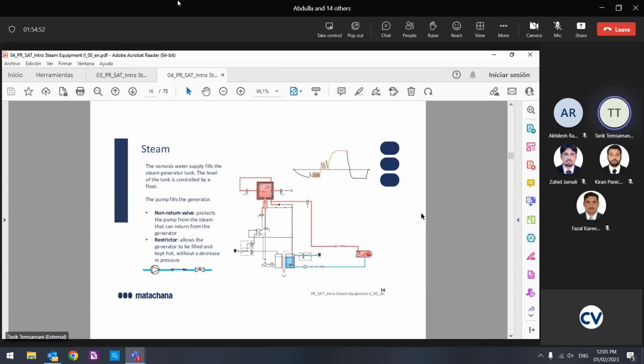Once the water reaches the maximum level, the heaters start working, and we start converting water to steam. Once the pressure in the steam generator is okay, we can fill the jacket. We open this valve and we send steam to the jacket. This happens with the machine on standby, machine on, but no cycles. This valve is always open, and this one is always working. So we have the machine ready to do cycles.